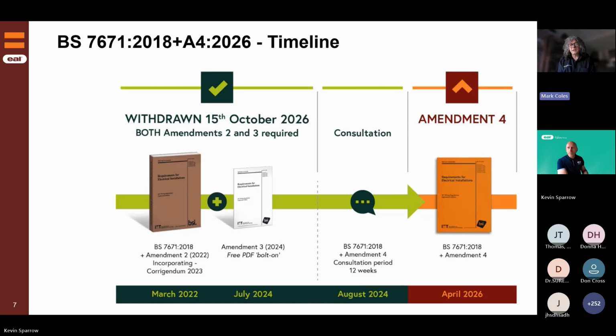We're on a fourth amendment, and conventionally with British standards you're permitted two amendments. But we had an amendment in 2020 that was about EV. Something came out of the woodwork, and BS 7671 had to react pretty quickly to take on that particular safety issue. Then we saw an amendment two years ago, in 2024, about bidirectional and unidirectional devices. That came out of the woodwork too, so something had to happen.